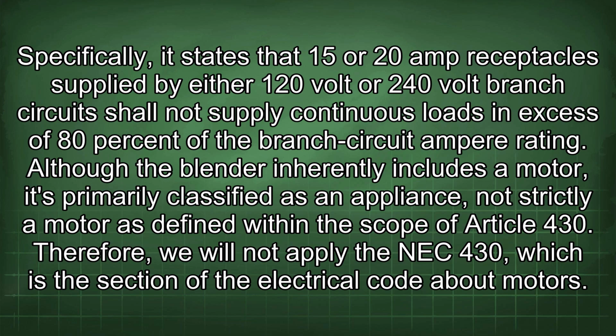Although the blender inherently includes a motor, it's primarily classified as an appliance, not strictly a motor as defined within the scope of Article 430. Therefore, we will not apply NEC 430, which is the section of the electrical code about motors.